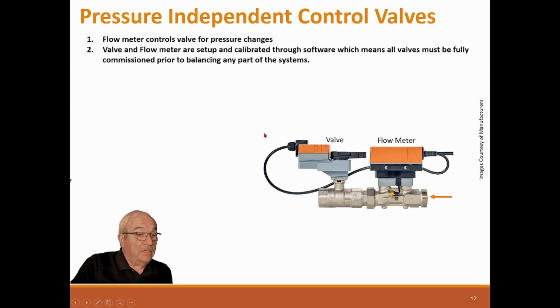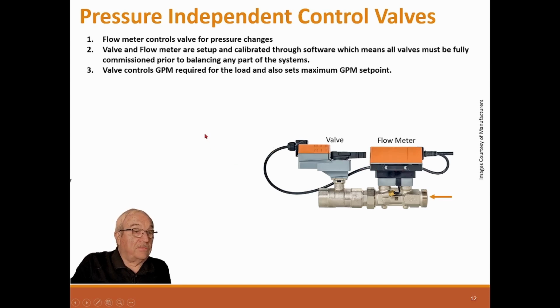As is typical, a lot of times the control contractor's not done when we're out in the field. For these things, they need to be done. They need to be fully commissioned, not just installed and programmed, but fully commissioned through that tool. Commissioning is never done when we're out there, but this needs to be done. This is one thing that's different. If you try to balance the system upstream with these running wild, you're not going to be successful.